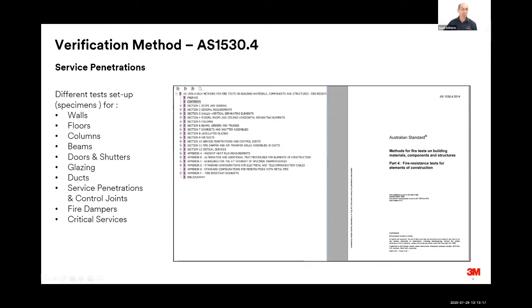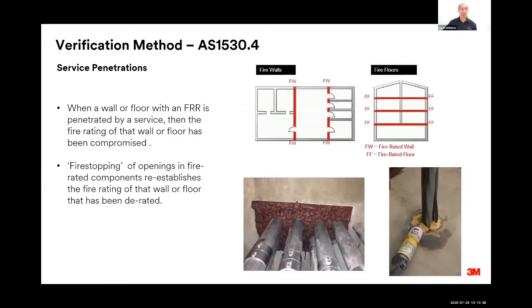AS 1530.4 describes quite a range of different elements from walls, floors, columns, beams, and in this presentation we're interested in ducts, and that's in section 9 of AS 1530.4, which describes the arrangements that are tested and the metrics. So ducts are actually fairly, in principle, similar to any other service penetration. Once a wall or a floor that has an FRR is penetrated, that fire resistance rating is no longer valid. It is compromised.